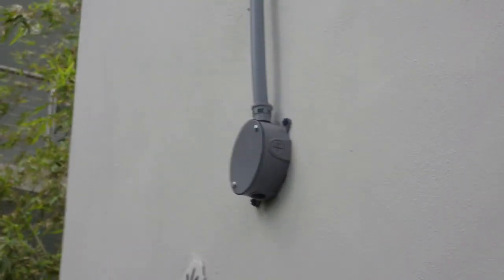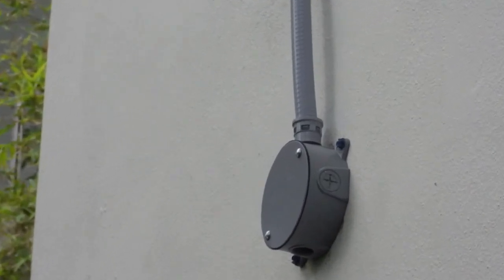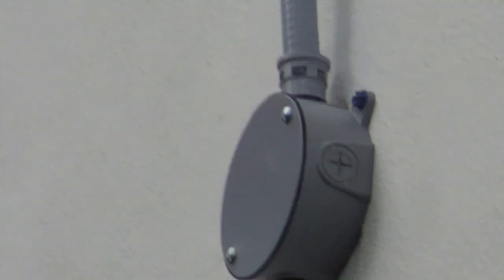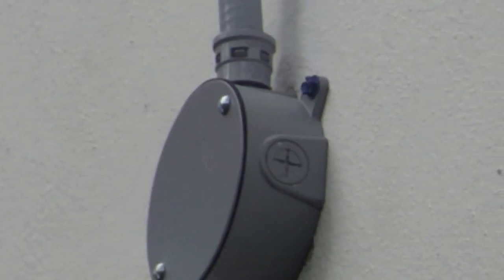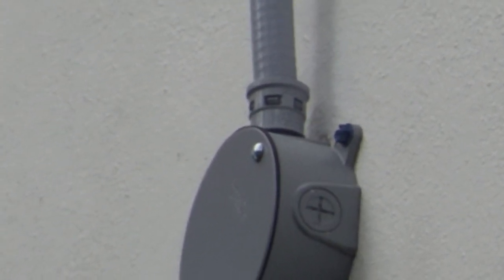That's a violation of 356.42. Those connectors are not listed for use with that raceway. Also, not enough supports.